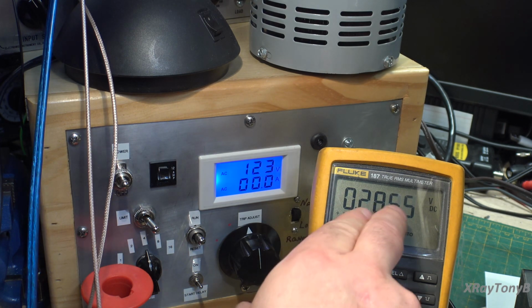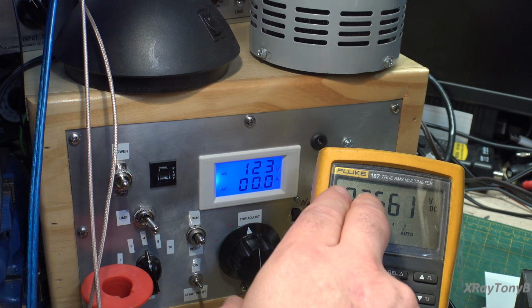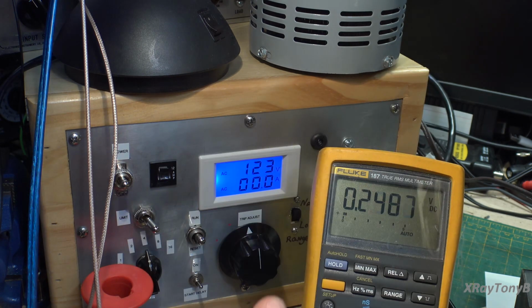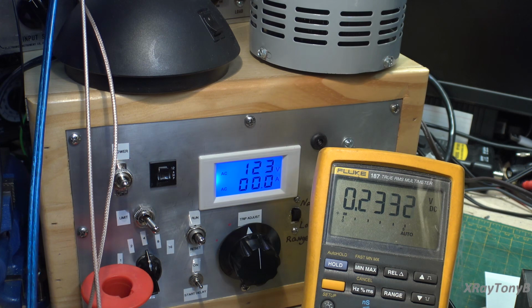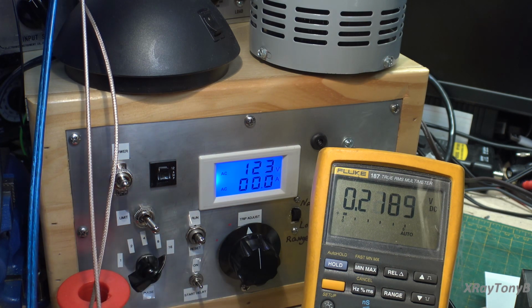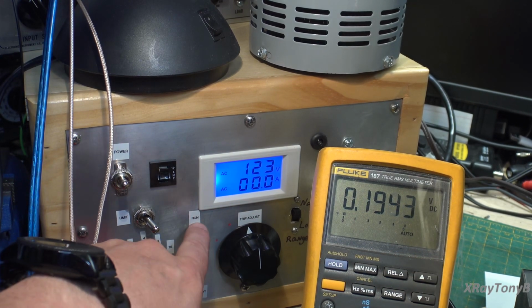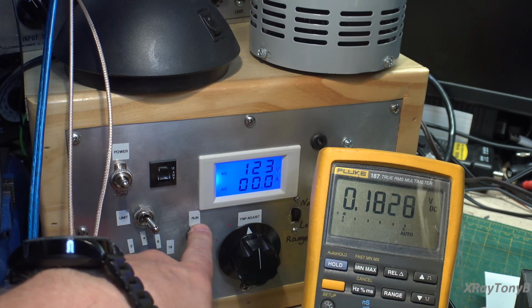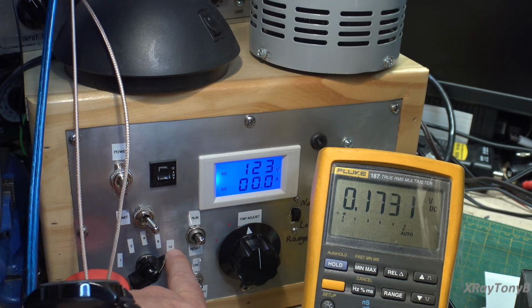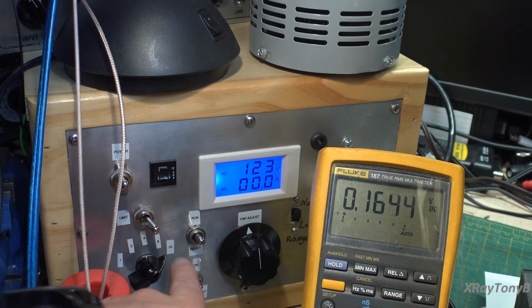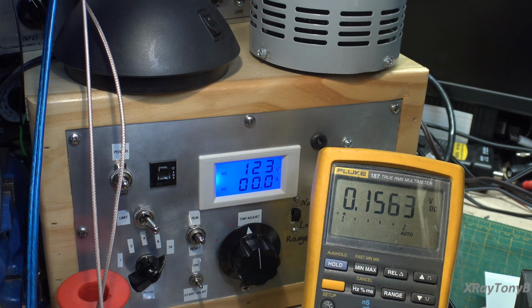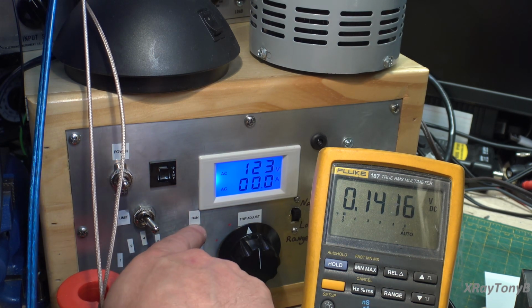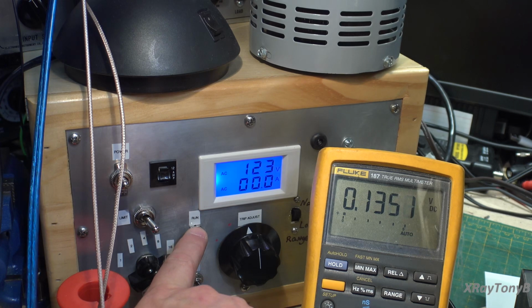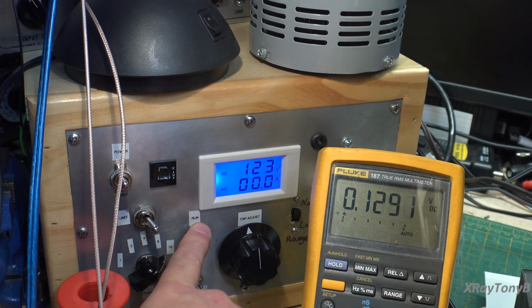We can't really see the voltage drop here with the short because it's happening so fast and this thing's shutting it off. So what I'm going to do is increase the trip time to give it a little more time to react, and we'll see what happens. Again, this is still only 16 cycles, and we're looking at 60 cycles per second, so it's still a fraction of a second of overcurrent. This is not a dead short, so I'm not really concerned about it. So here we go.